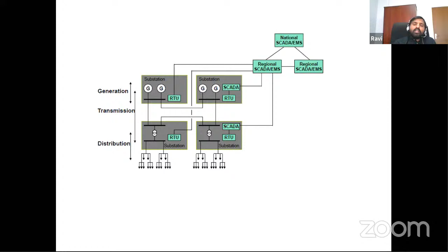Let's look at how we monitor and control a substation. We have different substations, each equipped with a remote terminal unit. The remote terminal unit senses the situation in its substation and transmits information to the regional SCADA center. From the regional SCADA center, information is transmitted to the national SCADA center. The RTU can take its own decisions, but sometimes needs control signals from the national or regional SCADA centers. SCADA centers improve control and monitoring operations.